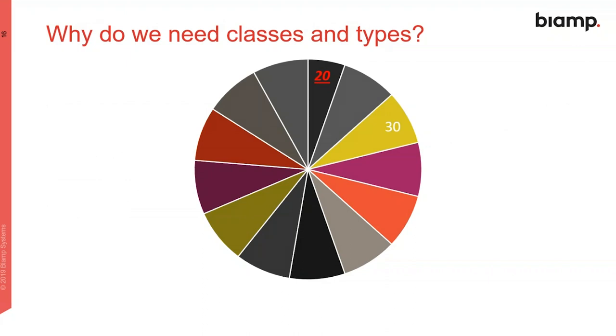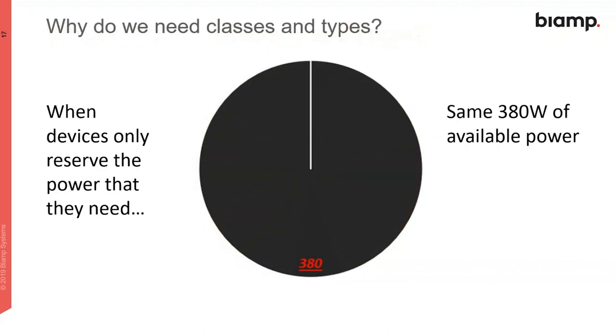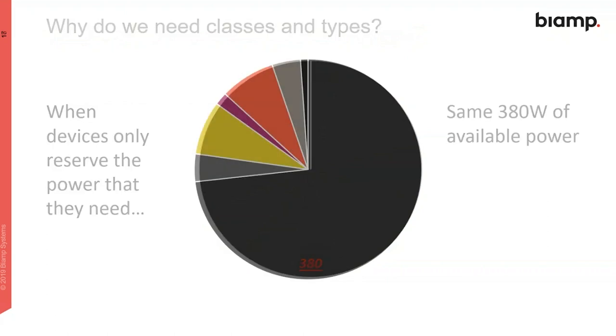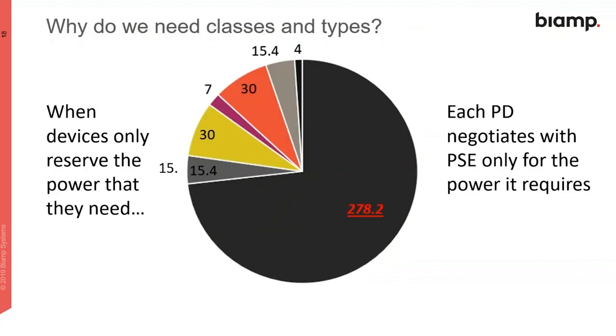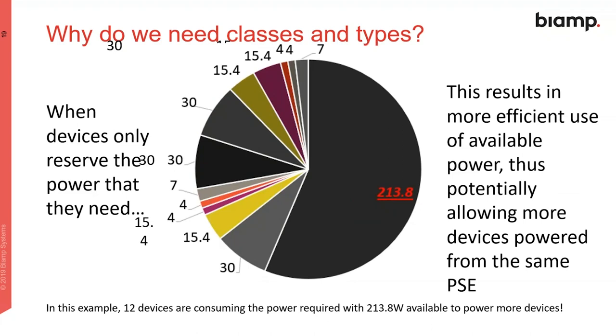So if we have devices that only require 3, 4, or 5 watts, but they're reserving 30 watts, then we're just wasting power budget. If we take that same 380 watt budget and break it up so devices only request the amount of power they need based on their class, then if we have a lot of low power devices, we can power more devices on the same switch, and we can mix and match. This gives us more efficient use of available power, and we can have more devices on a single switch if they're less than the maximum 30 watts.